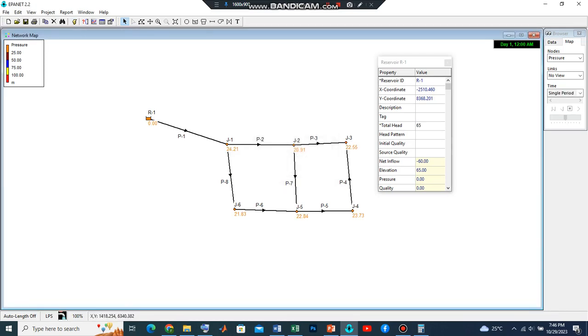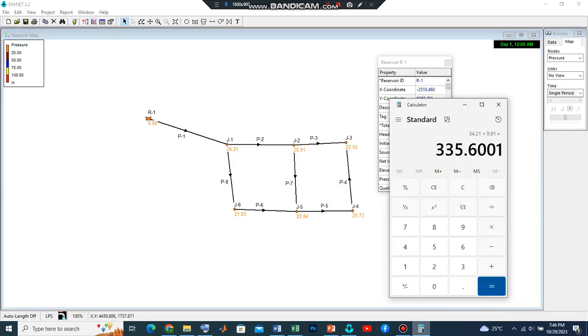So we can see that we have about 24, we have about 20. So let's look at our conversion. If we have 20, let's look at the lowest value here. This is 20.91, and we multiply by 9.81. What this should give us is about 205 kilopascals. Now remember, we said we needed to have between 250 to 300.